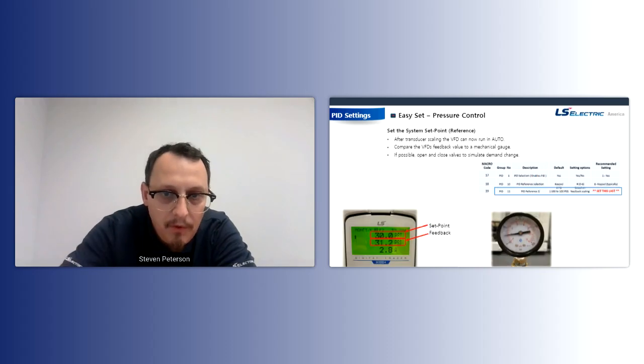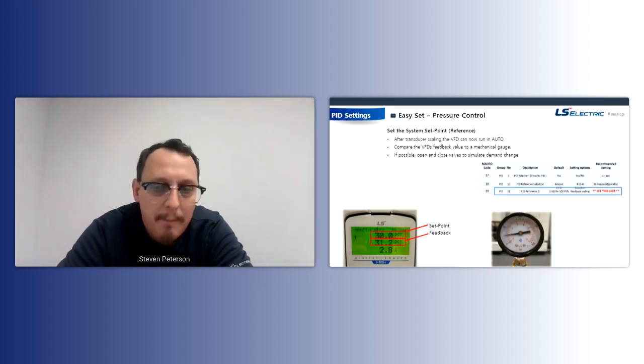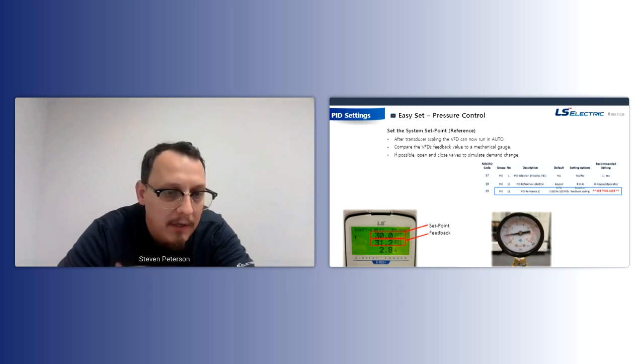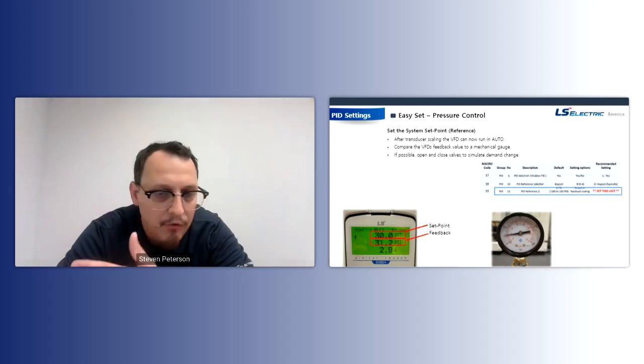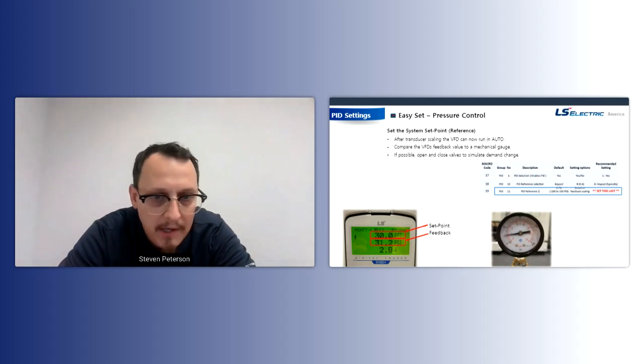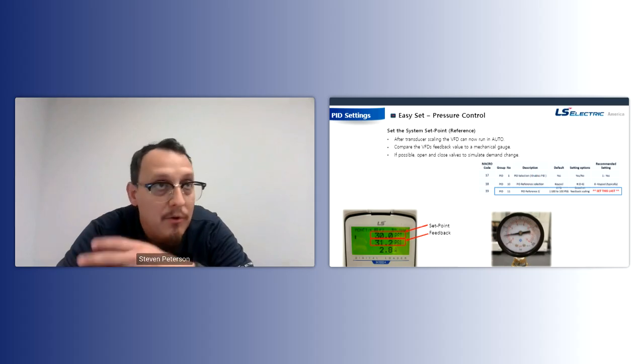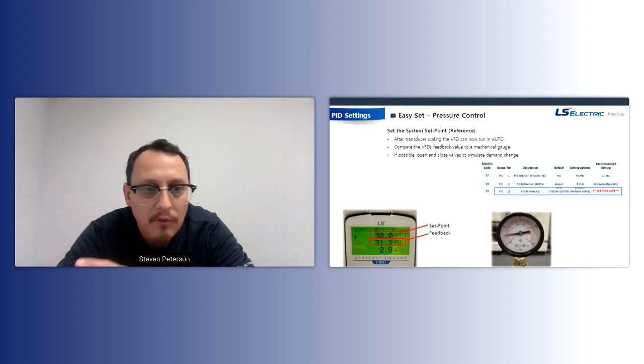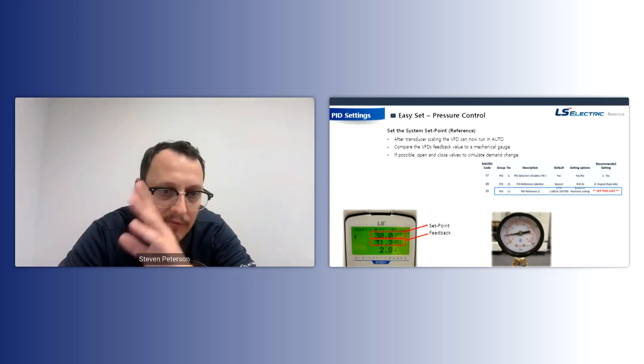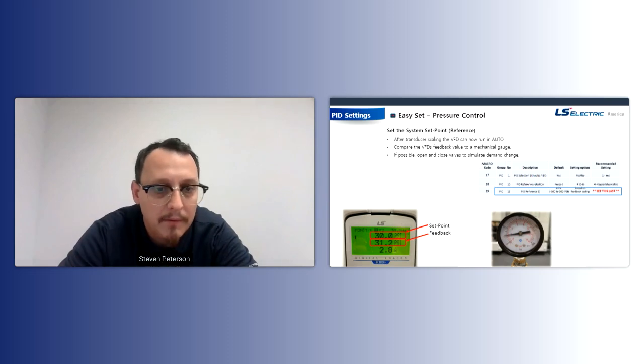Okay. So after you do your pressure scaling of 100 PSI, you could go to the next step, which is right here, setting up your set point. Your set point is what you want to maintain. I have a little picture down here where we're trying to maintain 30 PSI. It's a pretty low pressure that might be good for drip irrigation or something like that. Others of you doing commercial or municipal work might be running 60, 70 PSI or even higher.